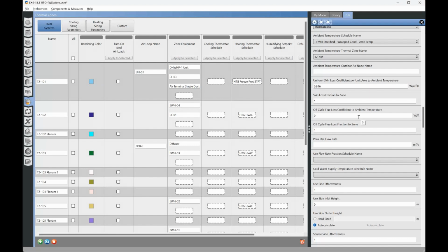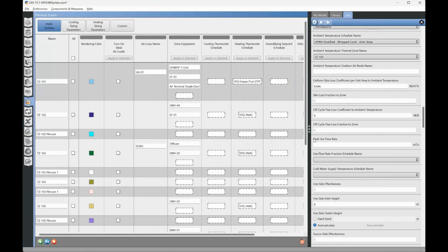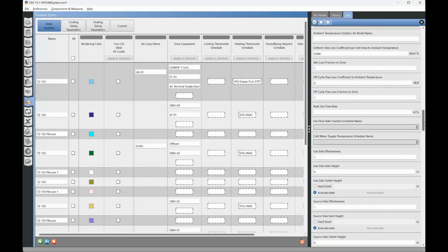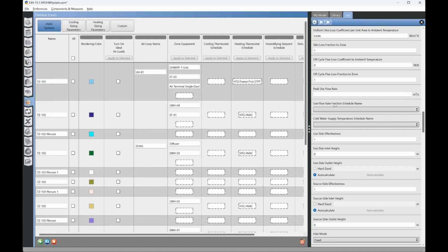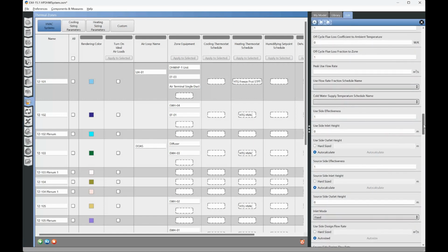Off-cycle flue loss coefficient, ambient temperature, flue loss. Yeah, I guess I'm not sure about that, and you can read up on more of this in the input-output reference manual. Peak use flow rate: this value would be used for auto sizing if you're going to auto size the tank, but we already hard sized the tank.